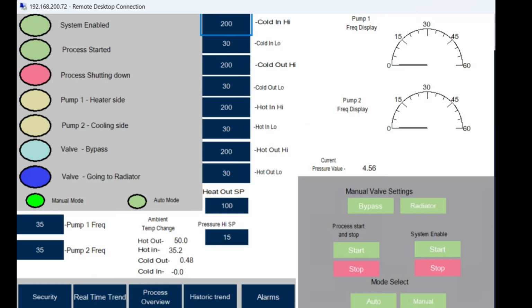And I'll just go ahead and go to the process controls. So we have lights over here saying if the system is enabled, if the process has started, if the process is shutting down, if pump 1 or 2 is on, and which way our valve is directing flow. And we have both of our pump frequencies that we can set, and then we have cold in high, cold in low, our temperature high and lows right here too that can also be changed. And then we have our heat out set point and pressure high set point too. And then we also have frequency displays for both the pumps and our current pressure value also right here too.